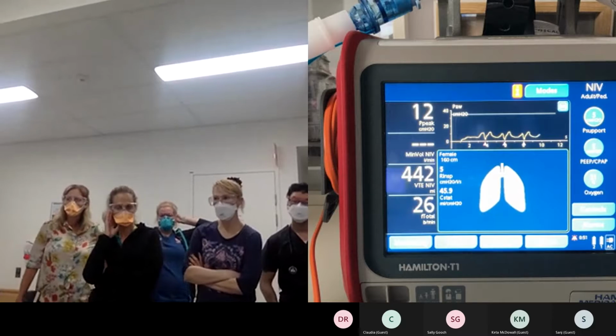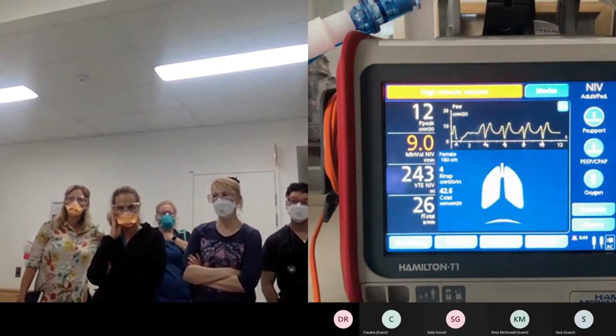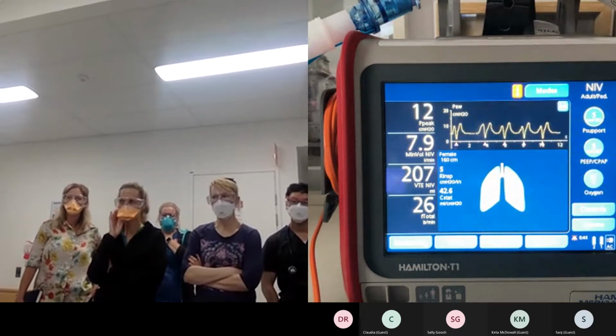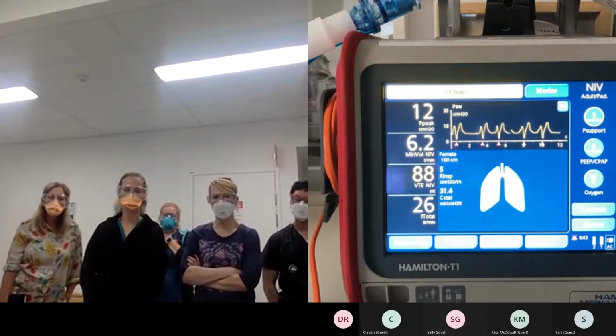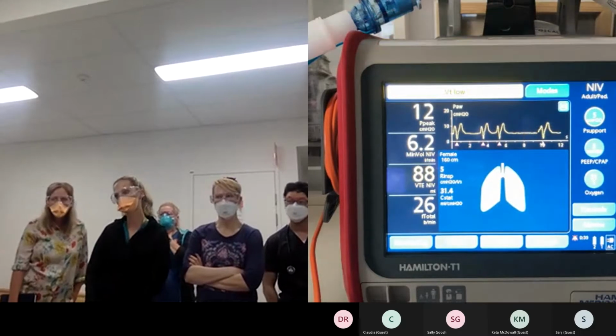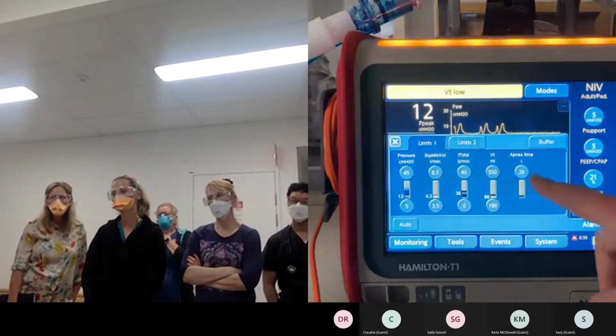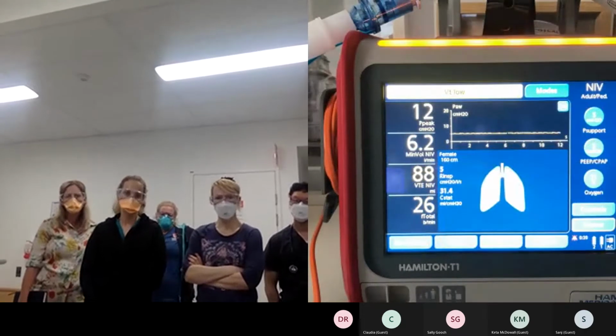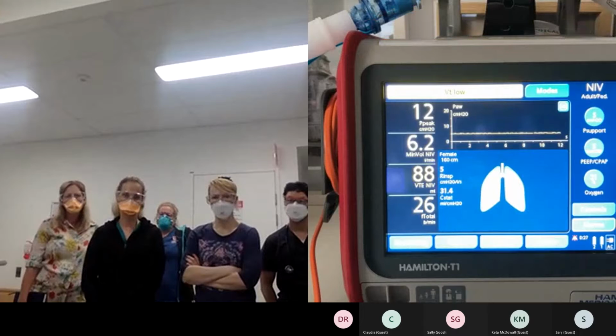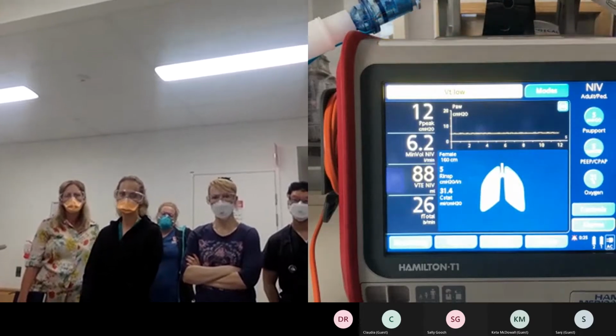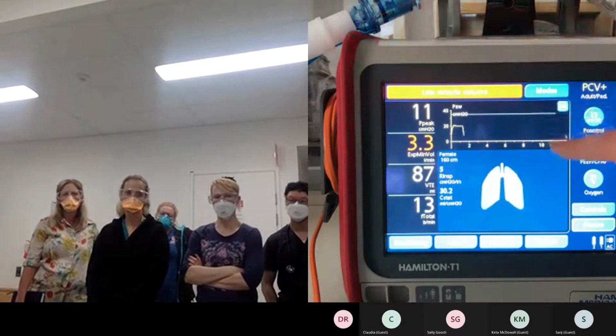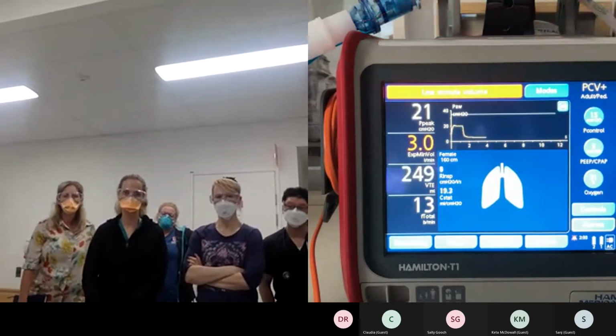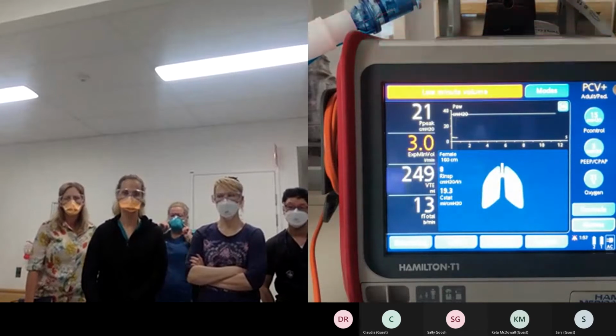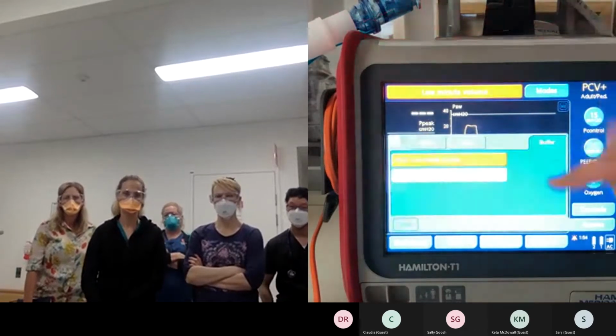Patient spontaneously breathing. You can see that you've got your peak pressure, which is the addition of these two, without being on a test lung. But if your patient stops breathing, what we've got down in alarms is an apnea time. It's defaulted at 20 seconds. So if the ventilator doesn't acknowledge a patient effort in that time, it will change over into apnea ventilation. You can see that we're now in PCV plus, so it's yellow, it's not white. You've also got apnea ventilation being an active alert.